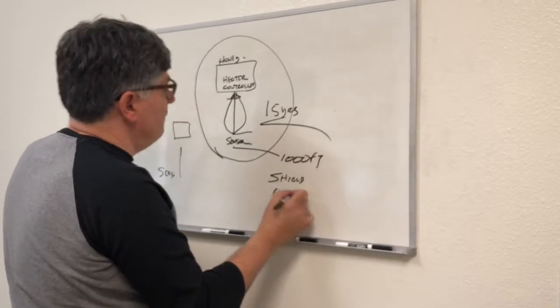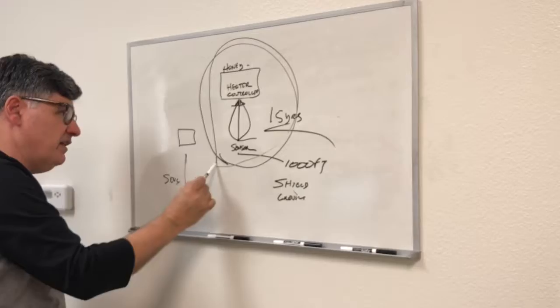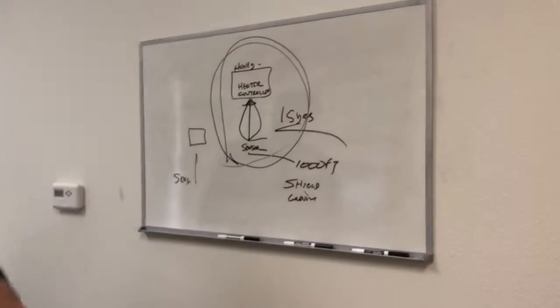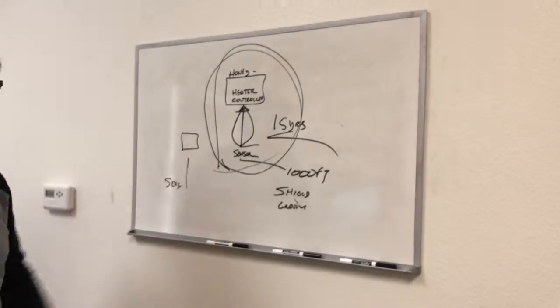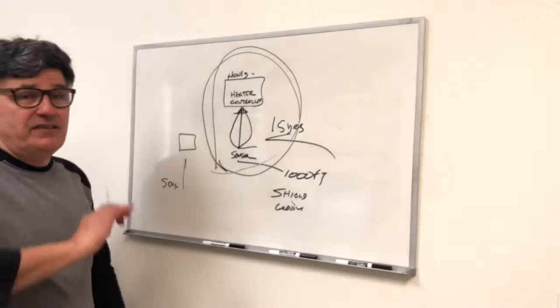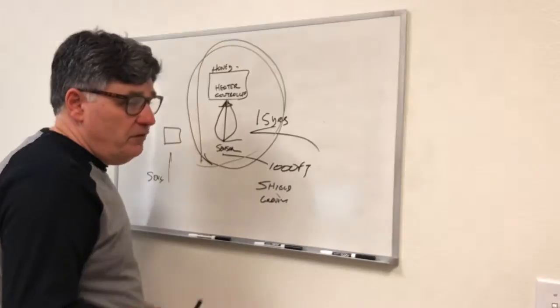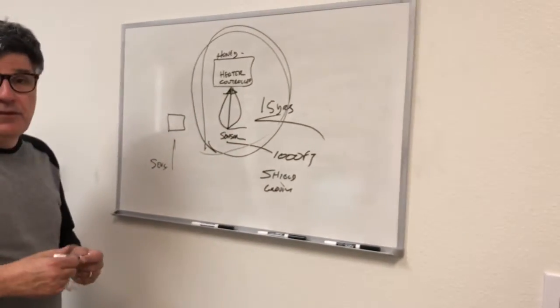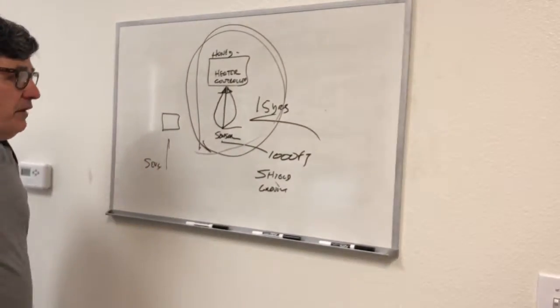So that's what I'm proposing - just mount these to the face of the existing control panel that's there, wire it up, and that's your heater control completely 100%. Then you can run VFDs all day and night and never see interference - not even a hundredth of a percentage point on the heater application.